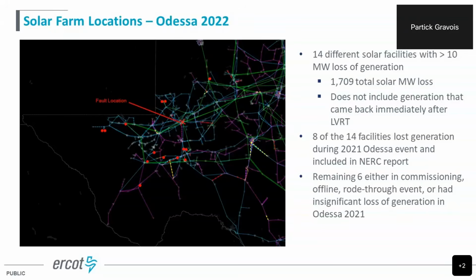this aggregate megawatt loss. But 8 of these 14 facilities also lost generation in the 2021 event. So only 2 of those 10 from 2021 did not repeat for this event. But here's your map. Fault location, same location, a somewhat smaller area. We don't have that one way up in the panhandle. That was due to the PLL loss of synchronism that was disabled. So they were one of the ones that rode through the second event but were involved in the first. For the remaining 6 of those 14, in 2021 they were either in commissioning, were able to ride through the event, or their megawatt loss was insignificant.